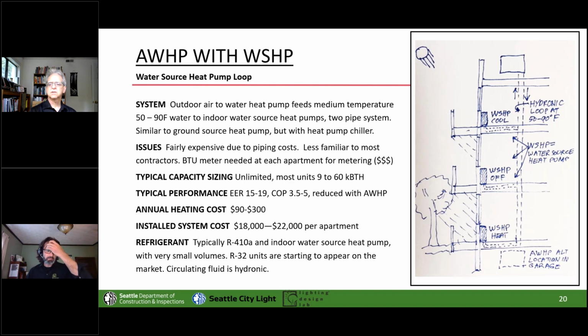So for, I don't know, from the 70s to the 90s, water source heat pump loops were very common. Two pipes, and you'd have a boiler and a chiller or a cooling tower, depending on your climate. So you had heat that you could put on the loop and heat you could take off the loop with the chiller or cooling tower. And then the water source heat pumps are packaged. They're a lot like package terminal units or the vertical terminal package units, but instead of an outside air, it just uses water to that boiler or chiller. And in this case, the temperatures it needs are perfect for a water source heat pump.